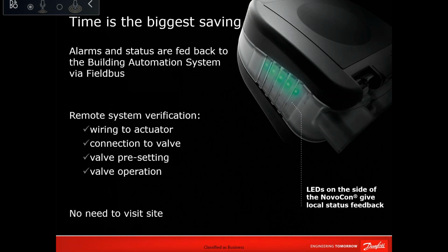Next question is, do we need additional temperature sensors for delta T control? No. Whatever you will be having with the Novocon, there will be two temperature sensors. For the small size Novocon S, you have 2 built-in temperature sensors. For the medium size Novocon and the large and extra large Novocon, you have a 3 temperature sensor provision. You can use one for supply, one for return, and the other one is free. You can put it on the return air, you can put whatever. So yes, you don't need an extra temperature sensor to control delta T from Novocon. It has its own.